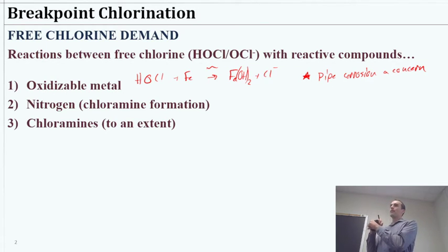But we'd rather that than having them deteriorate, leaching away the metals, eventually exposing it to open groundwater, contaminated sources, and potentially leaching lead particles off of really old pipes. So we protect against all of that by causing the water to be slightly on the scale of forming the mineral scaling deposits rather than corroding. So that's the oxidation reduction sort of stuff. Okay, so oxidizable metals demand some chlorine.